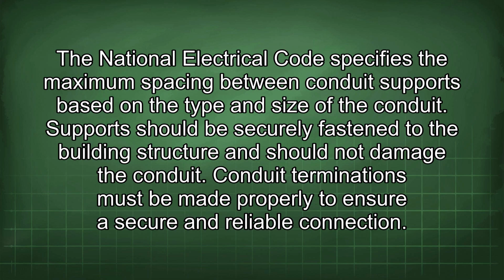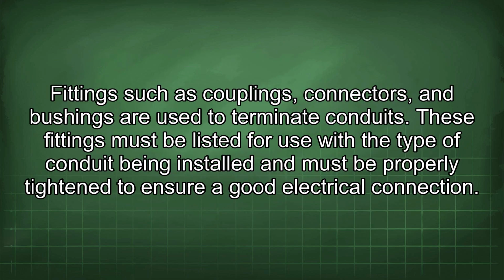Conduit terminations must be made properly to ensure a secure and reliable connection. Fittings such as couplings, connectors, and bushings are used to terminate conduits. These fittings must be listed for use with the type of conduit being installed and must be properly tightened to ensure a good electrical connection.